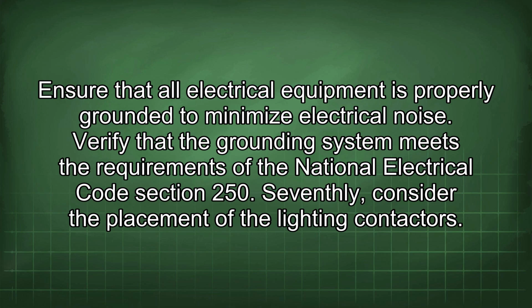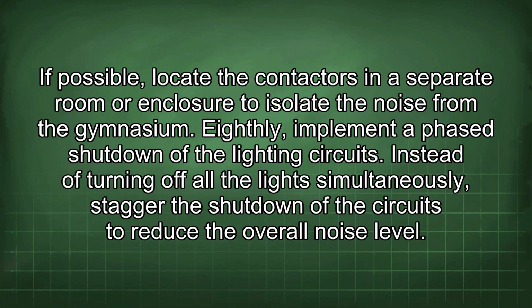Seventhly, consider the placement of the lighting contactors. If possible, locate the contactors in a separate room or enclosure to isolate the noise from the gymnasium. Eighthly, implement a phased shutdown of the lighting circuits. Instead of turning off all the lights simultaneously, stagger the shutdown of the circuits to reduce the overall noise level.